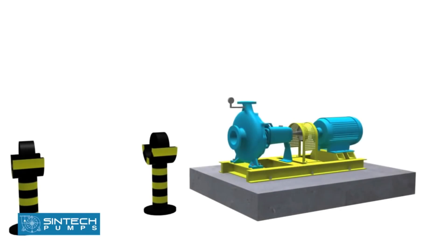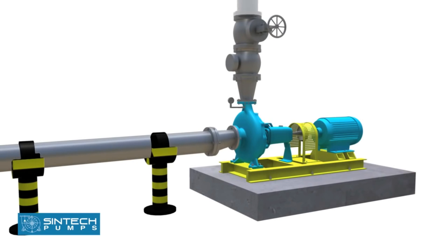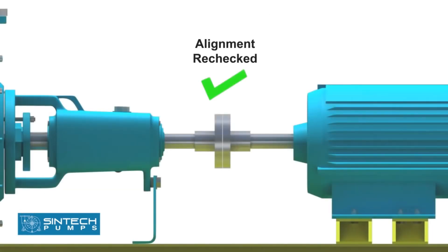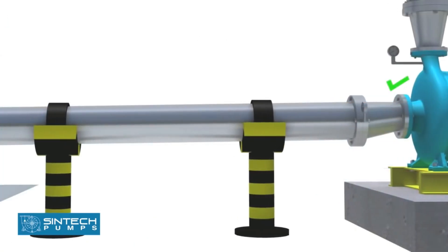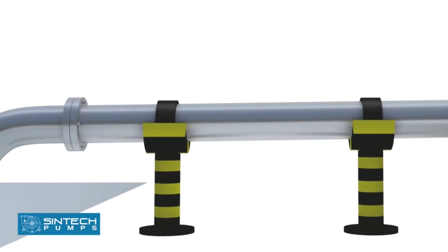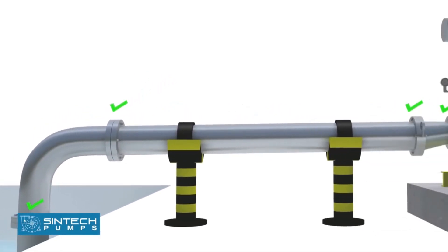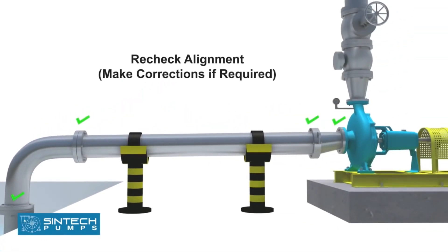After the alignment is completed, the piping associated with the pump should be bolted. Once this is completed, the alignment should be rechecked and similar readings should be obtained. If this is not the case, then the piping should be investigated and suitable corrections should be made. If this is left unattended, it can cause stress on the pump casing.